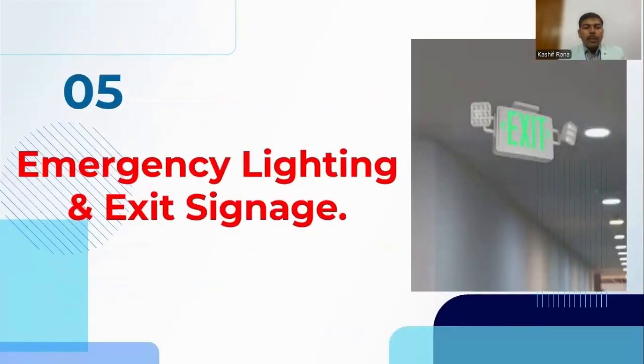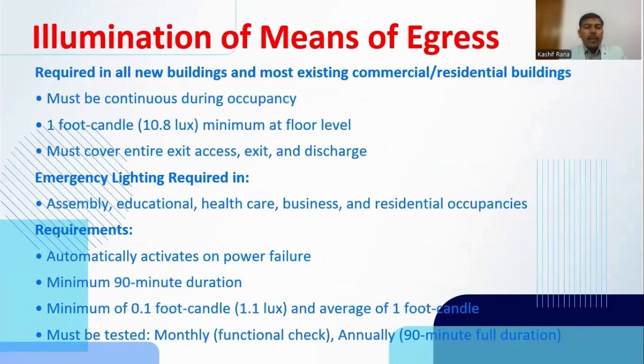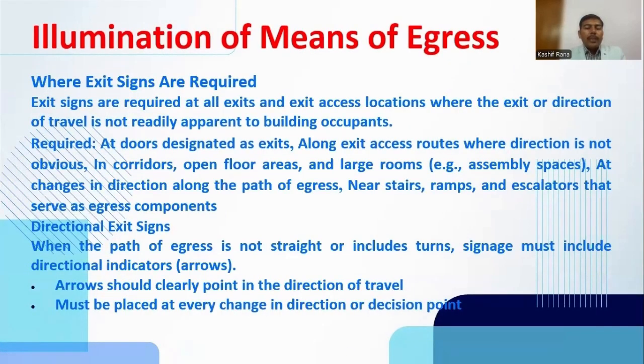There is another important topic: emergency lighting and exit signage. Emergency lighting is required on a floor when it is occupied, especially at the time of power failure. It requires a minimum of 1 foot-candle at floor level and must cover the entire exit access, exit, and exit discharge areas. It is required for all assemblies and all occupancies. The requirements: it should activate automatically on power failure, with a minimum backup duration of 90 minutes, and minimum 1.1 lux at every level of the floor. Exit signage is required, especially at exits and where there is a change in direction in the travel path.